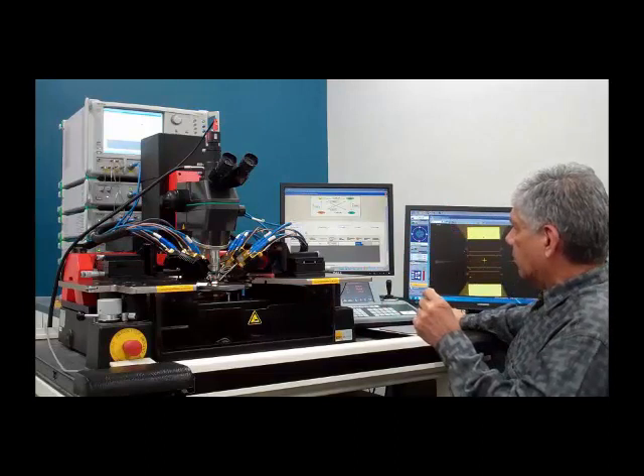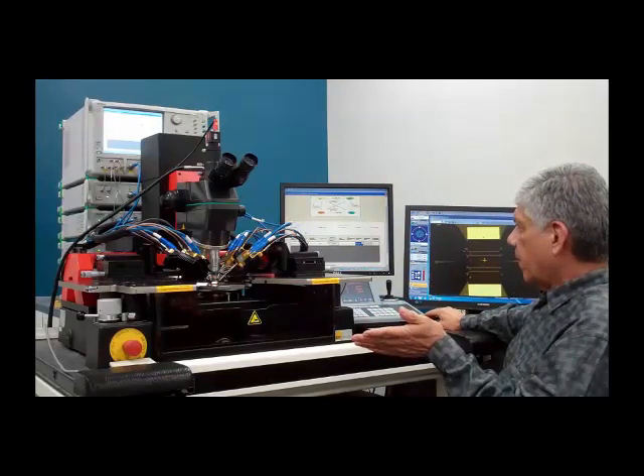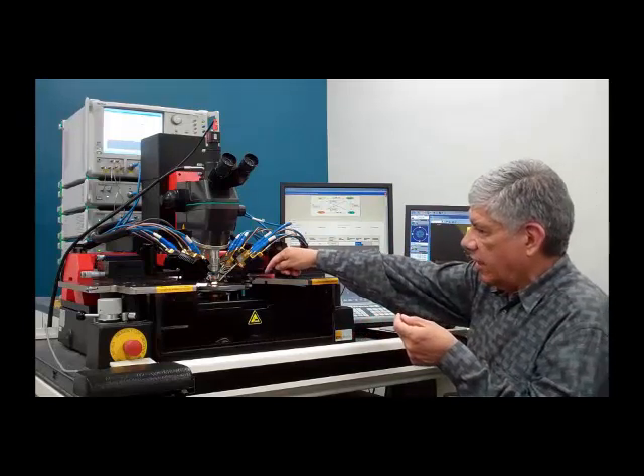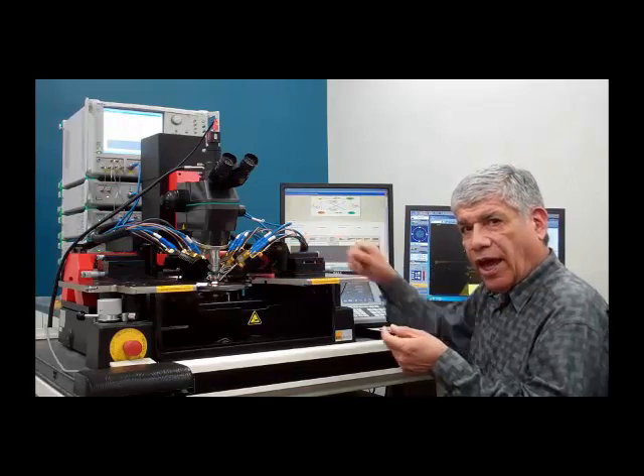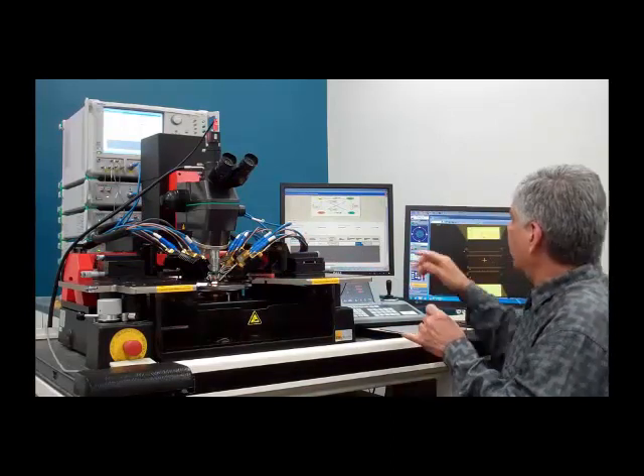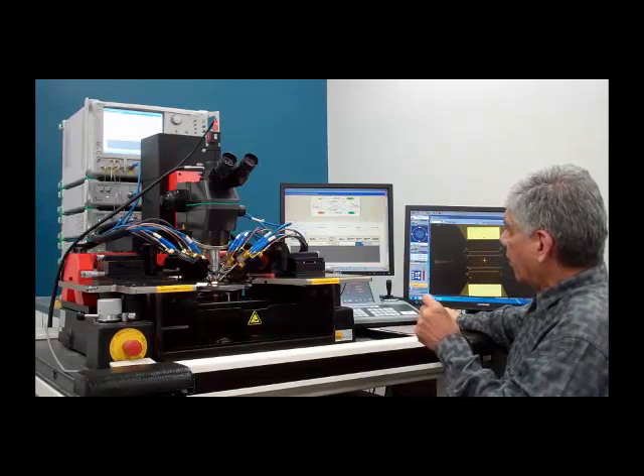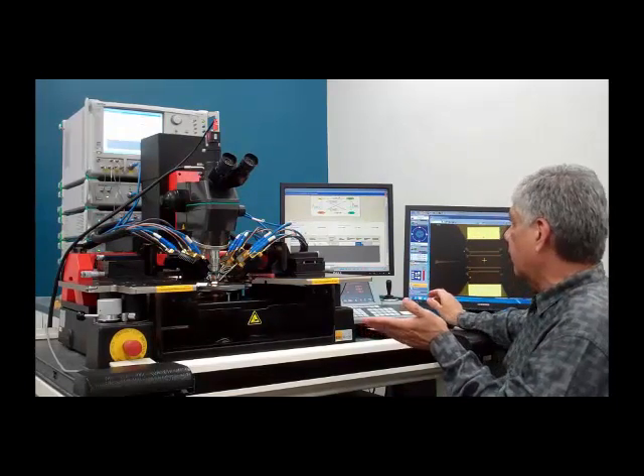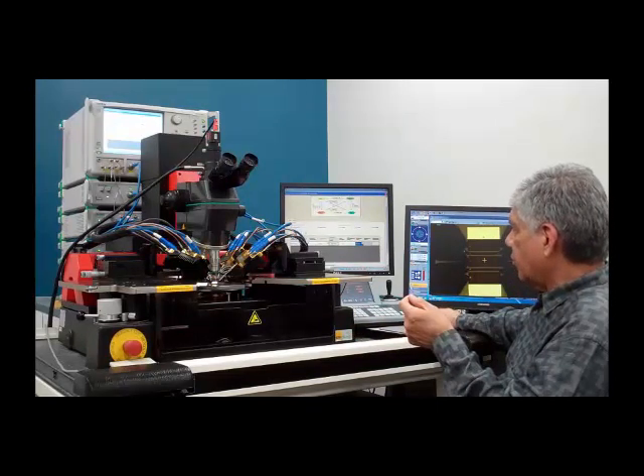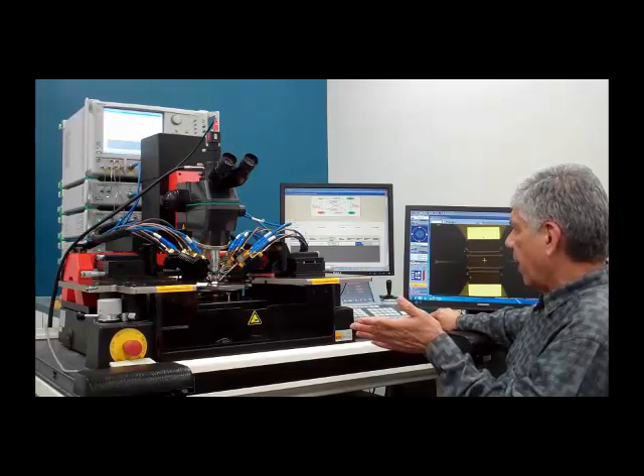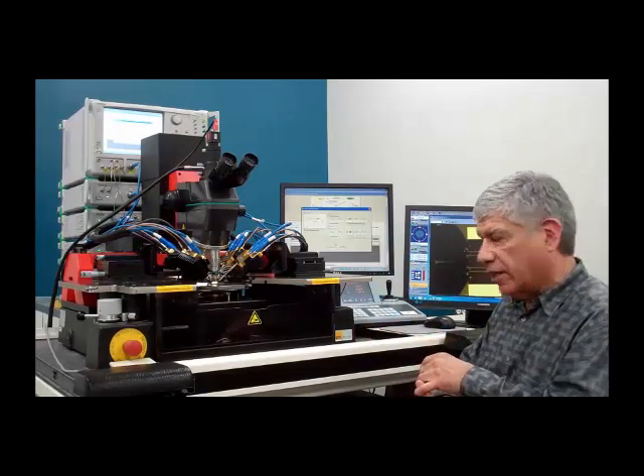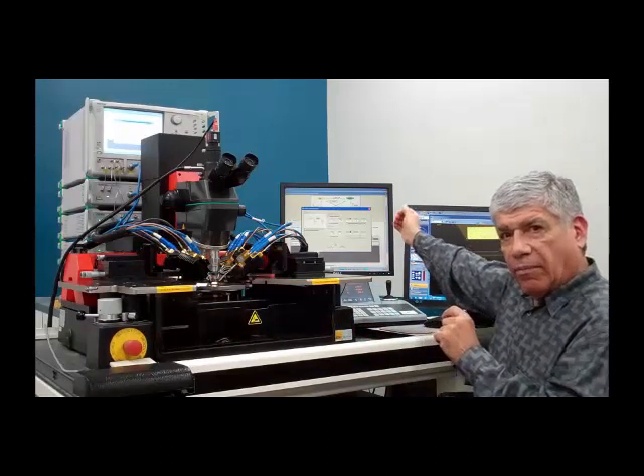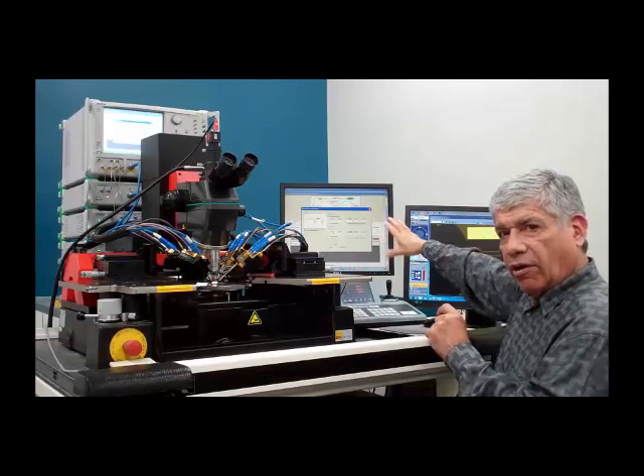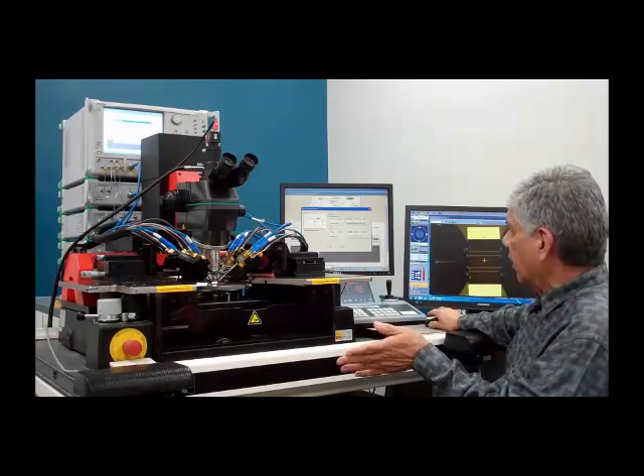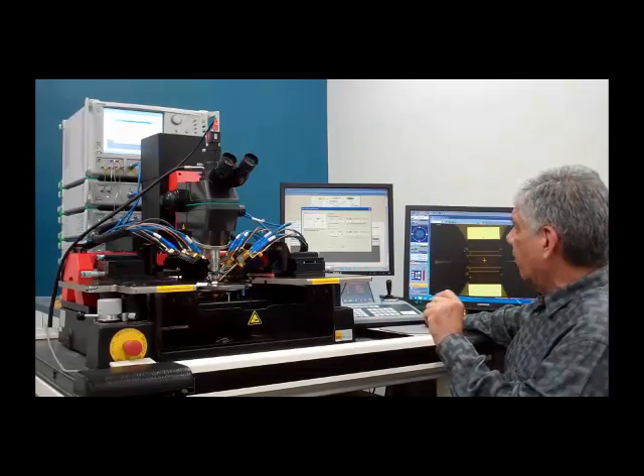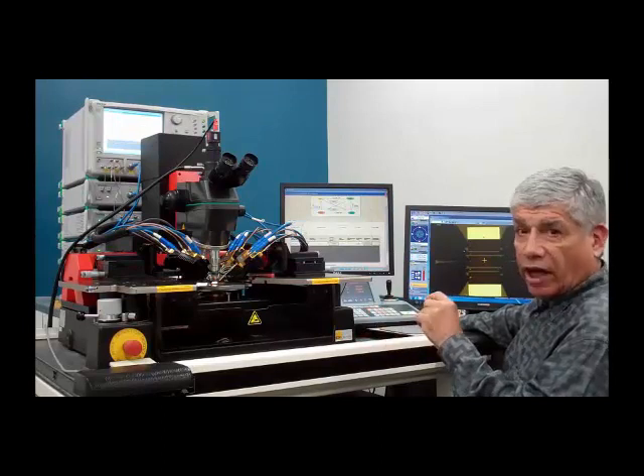Then the other things that we will set up are the line description. So in this case, the CS2 GGB cal substrate has a delay of 4 picoseconds. And so we set up for the delay of the line and enter 4 picoseconds for that line length. Then for the match, we define that we're using a match, and we can improve on the model of the match by entering the coefficients of that match or that load into our algorithm. And so this is where we would input the coefficients of the load and use that during our calibration.